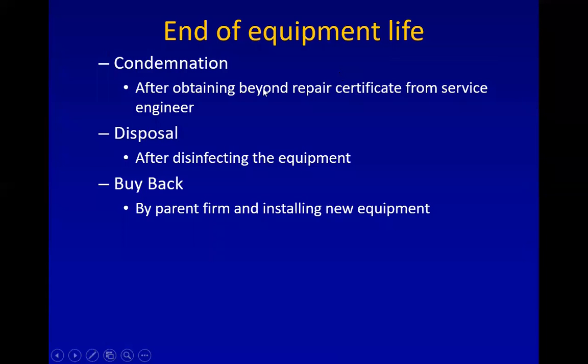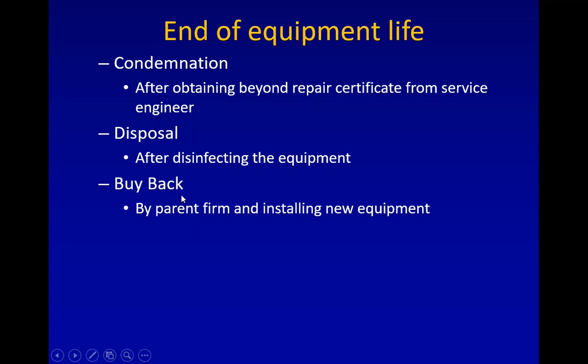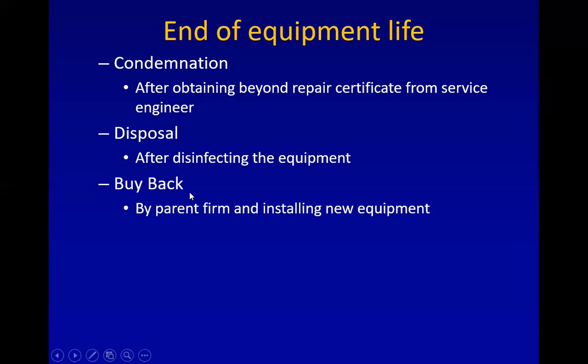Finally, at the end of the equipment lifecycle, the equipment needs to be condemned. It can only be condemned after obtaining a beyond-repair certificate from a service engineer, who certifies that the equipment can no longer be used. Before disposing of the equipment, it should be disinfected, as in a clinical laboratory equipment may be contaminated with clinical material. The equipment can then be either disposed of or sold back to the parent firm in a buyback offer, where the firm installs new equipment at a discount.